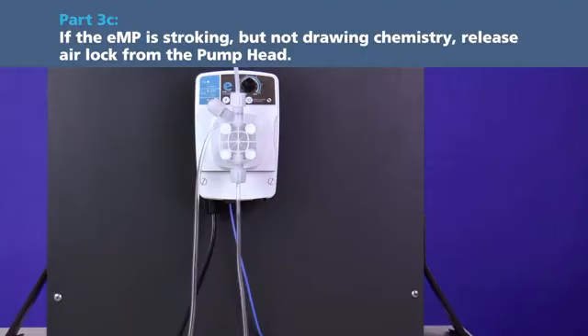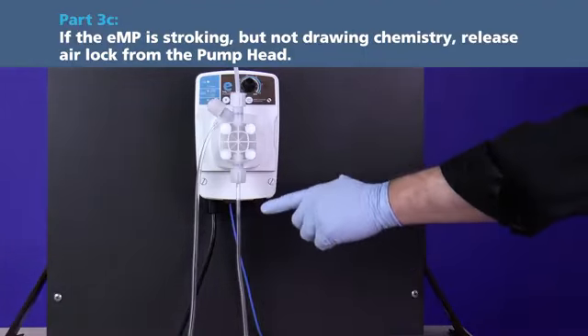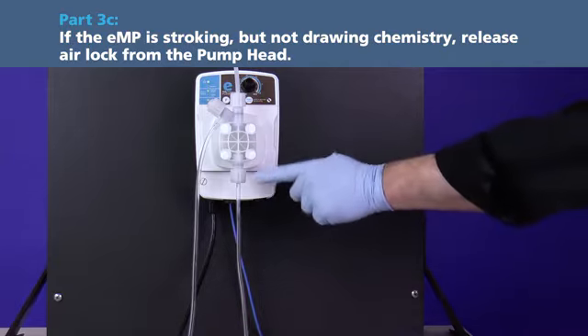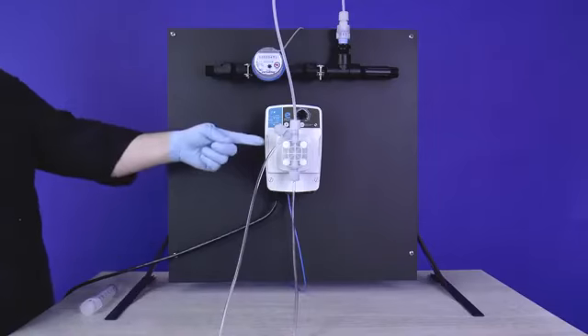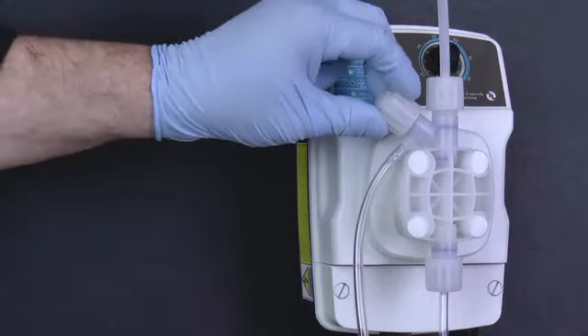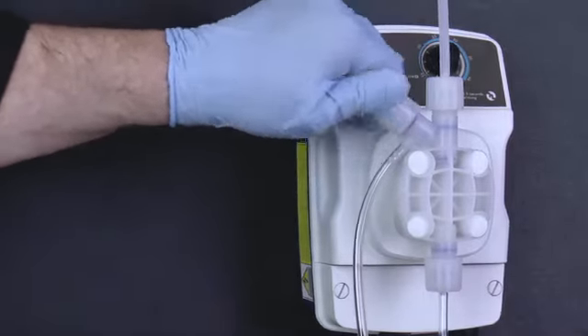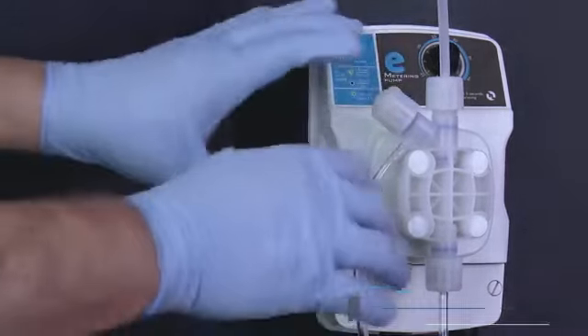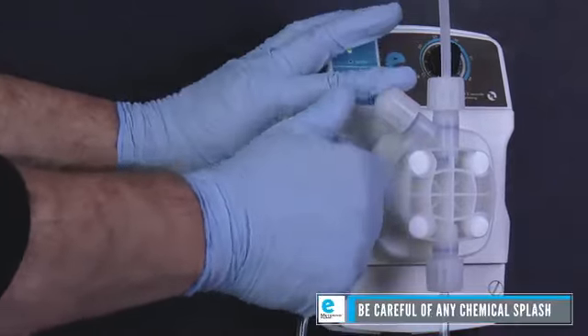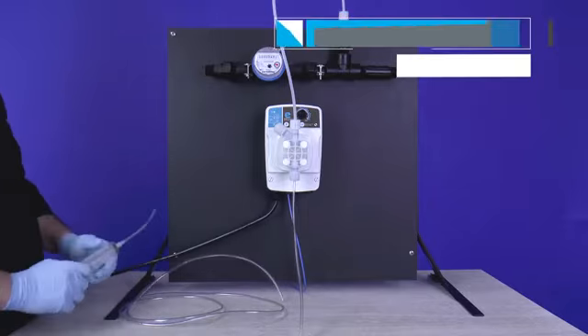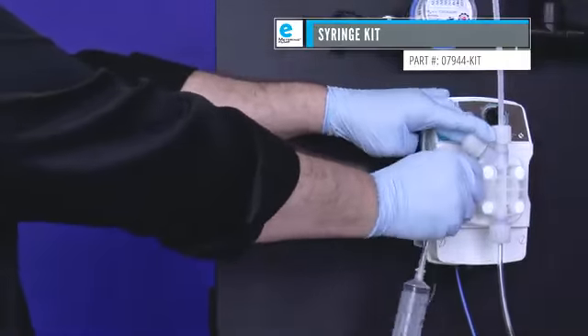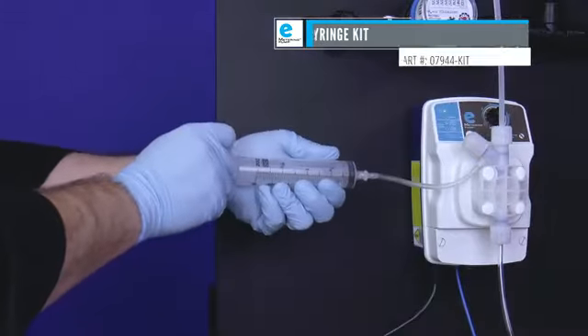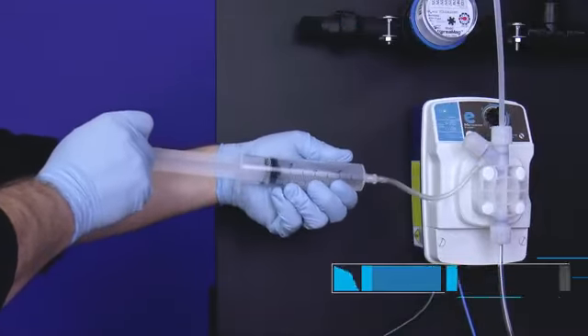Part 3C. If the eMP is stroking but not drawing chemistry, release airlock from the pump head. Locate the air bleed valve on the upper left portion of the pump head and open it by turning the valve counterclockwise. Remove the bleed-off tubing from the air bleed barb and set it outside of the chemical bucket. Using the syringe kit, slide the 4mm adapter of the syringe onto the air bleed barb and draw the plunger back. Chemistry should enter the syringe.